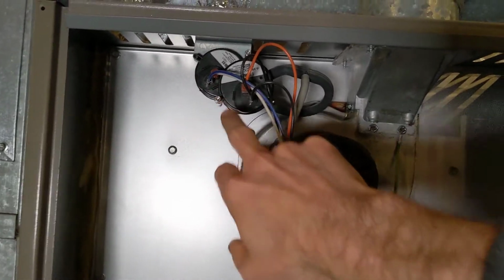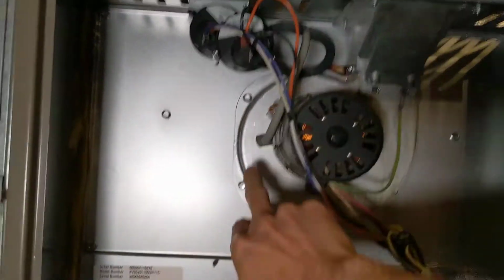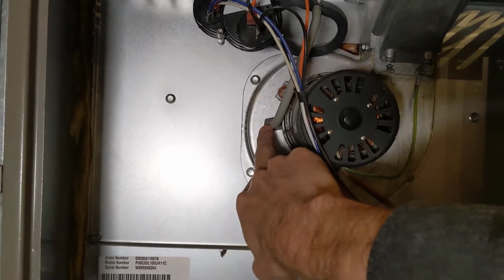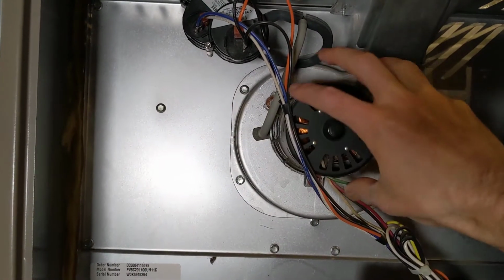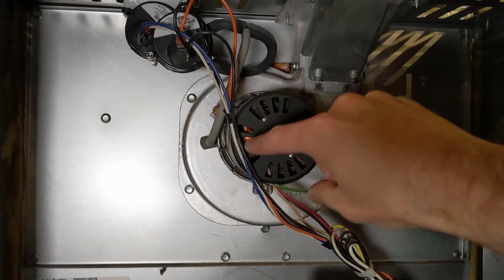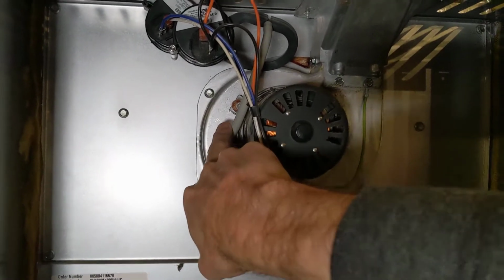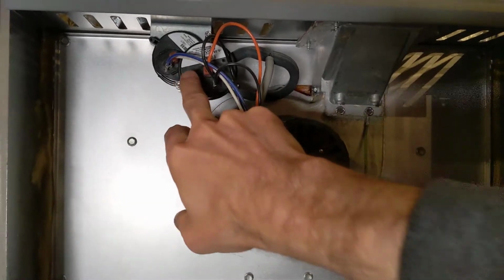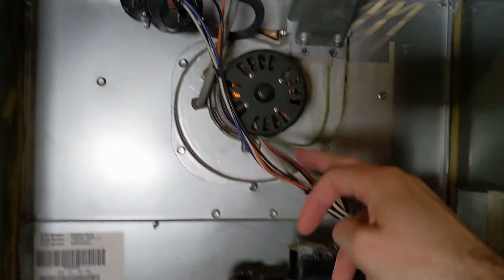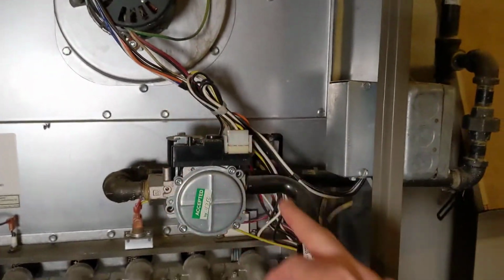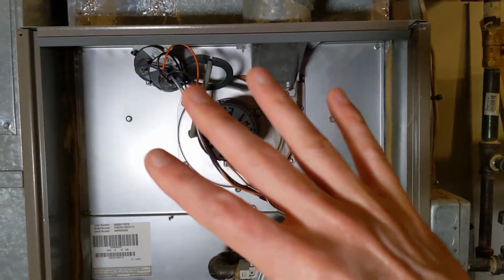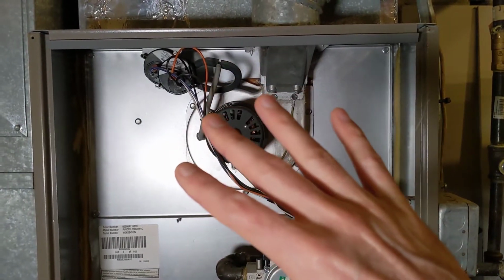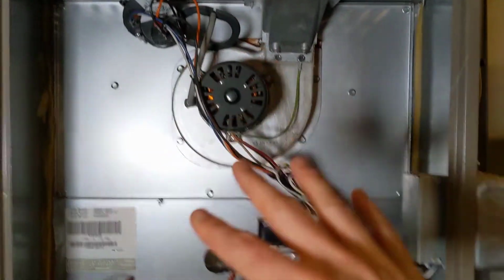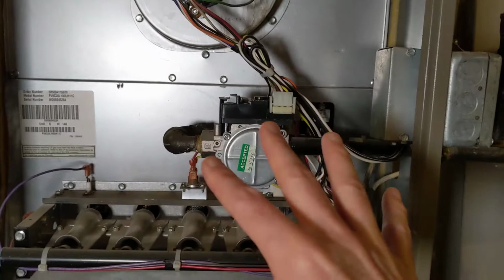These are called pressure switches, and this tube here is going into this little port. Once this motor creates a draft, it will suck in on this tube, and these switches will close. These switches are hooked up to the board through this wiring here. That will confirm to the board that we have inducer draft. So once we have inducer draft, then the gas can start up.